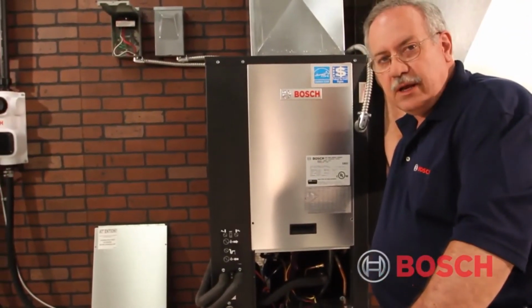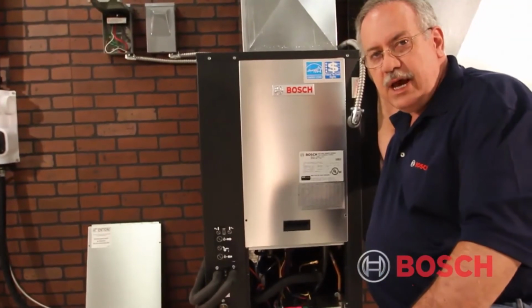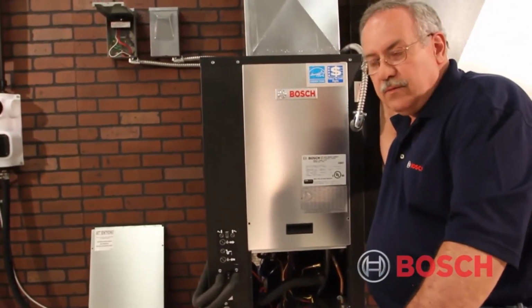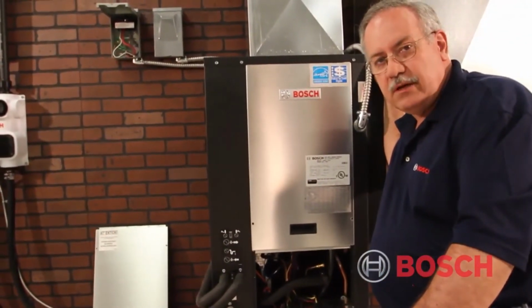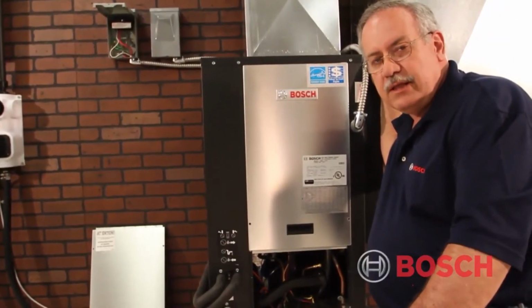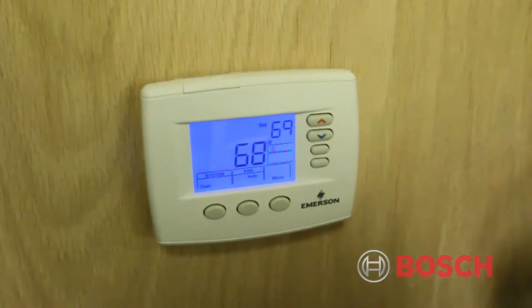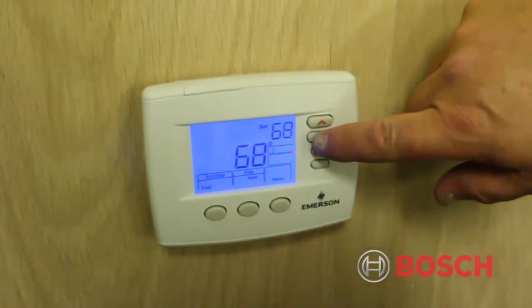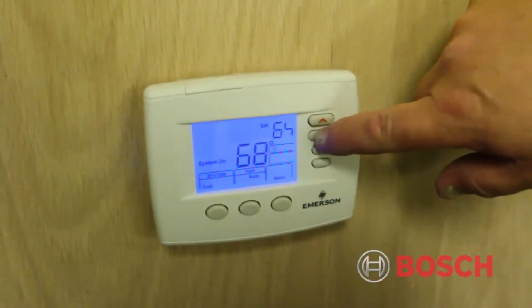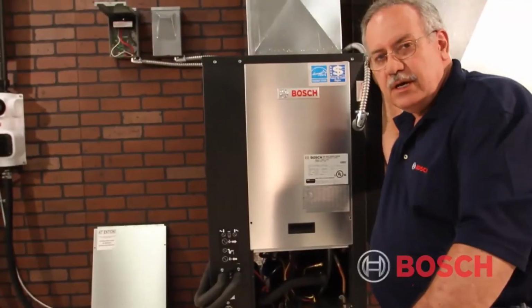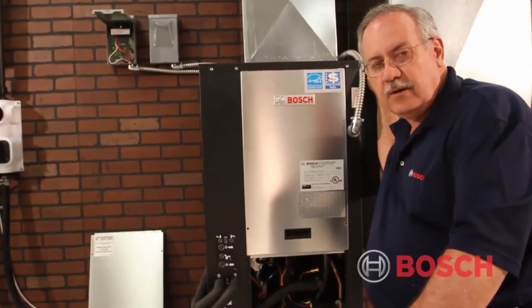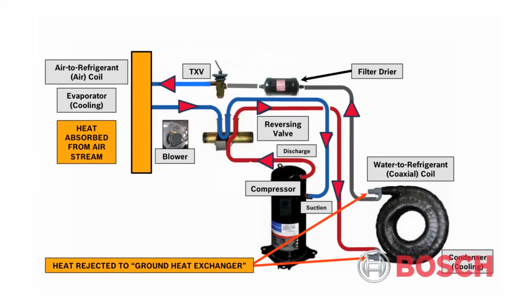We'll energize the unit. Now we always want to check a geothermal heat pump after it's been running for approximately 10 to 15 minutes. The first thing that I would always do is energize it in the cooling cycle and let it run for a few minutes, even if I'm checking it in the winter. The reason for this is because in the refrigeration process in the cooling cycle, the refrigerant that may have air and non-condensables in it hits the molecular sieve dryer, bidirectional dryer, in the refrigerant circuit first, helping remove any condensables that might be in it.